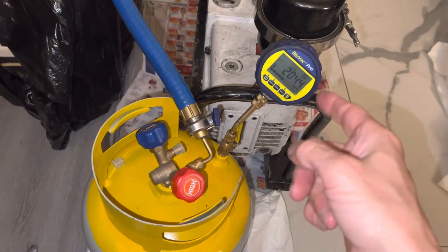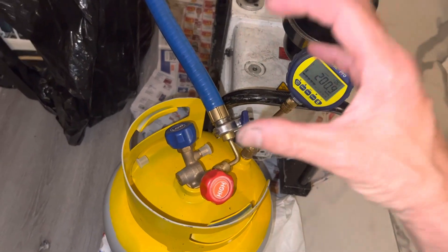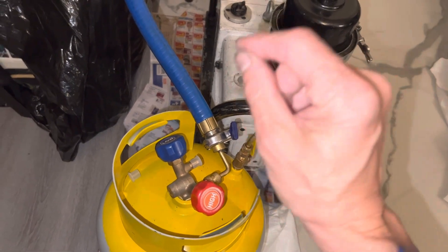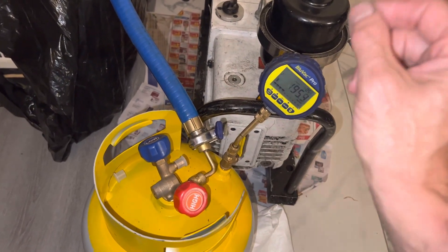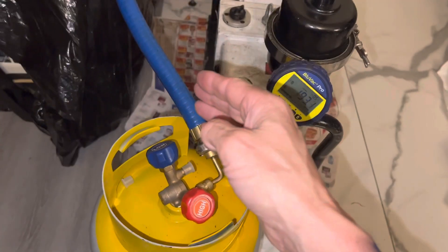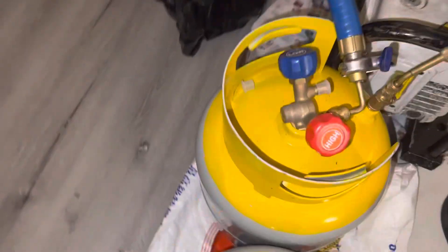I had to make this short video because I want to show for the guys who got micron gauges, whether they're independent or they're inside, say, the Fieldpiece manifold. When you're going through rubber hoses and you turn off the system and you're reading a micron gauge inside a refrigerant manifold, your rubber hoses will greatly affect how the rise of your micron meter reading is.